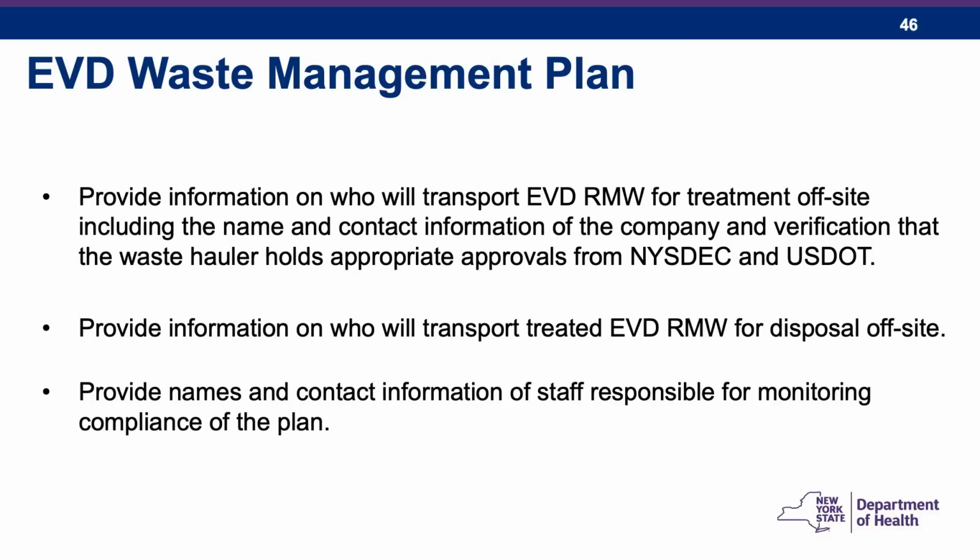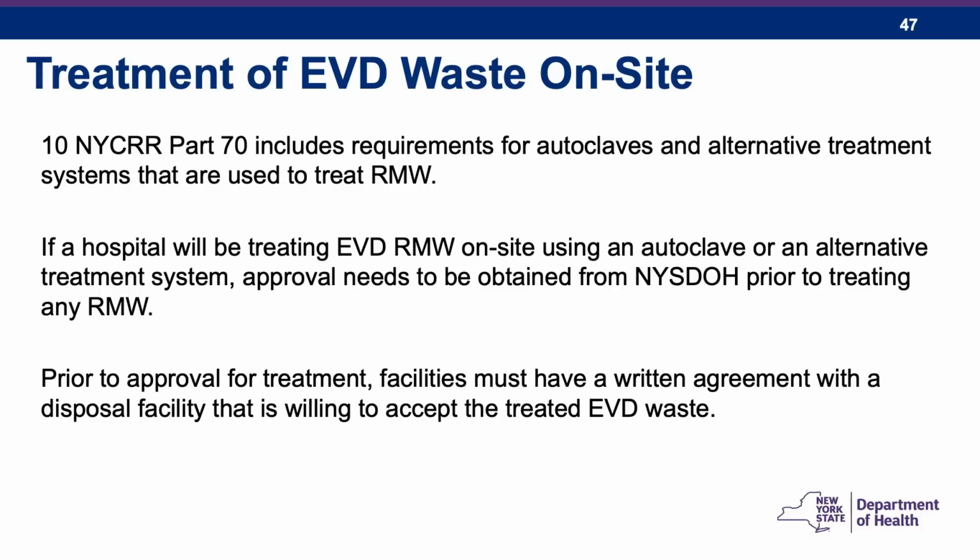You must have a written agreement with a disposal facility that is willing to accept any of that treated Ebola virus disease medical waste. So a hospital or a clinical laboratory that uses an autoclave to treat medical waste, when you start thinking about Ebola medical waste, you have to ensure that the autoclave is properly validated for the types of waste and the way it's packaged. Because of the more stringent packaging requirements, the normal autoclave procedures may not be effective in treating that waste. Also, we have situations where suction canisters might not be effectively treated using normal operating procedures for an autoclave.